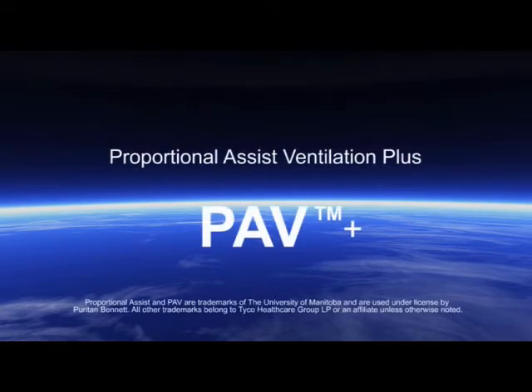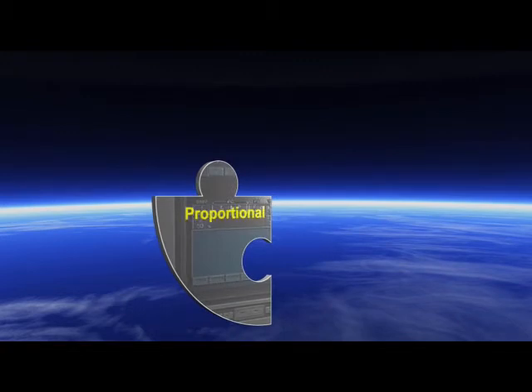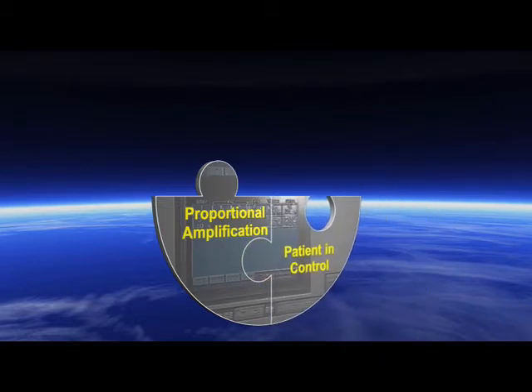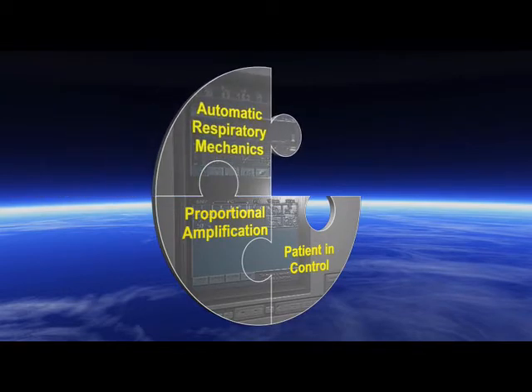Proportional Assist Ventilation Plus, or PAV Plus, is a form of synchronized ventilator support in which the ventilator generates pressure in proportion to instantaneous patient efforts. The ventilator simply amplifies inspiratory effort. Unlike other modes of partial support, there is no flow, pressure, or tidal volume set. PAV Plus's objective is to allow the patient to comfortably attain whatever breathing pattern his or her control system desires. The main goals of PAV Plus are synchrony and adaptability through the automated measurements of both demand and respiratory mechanics.